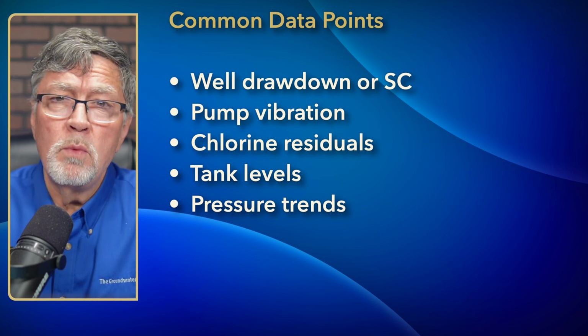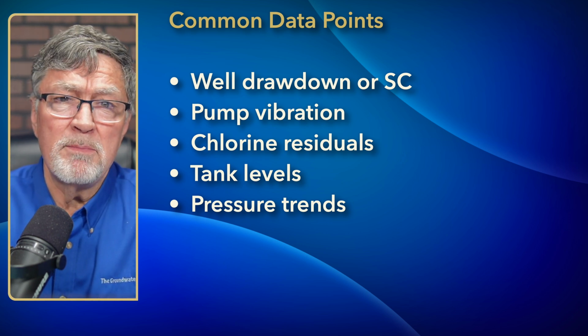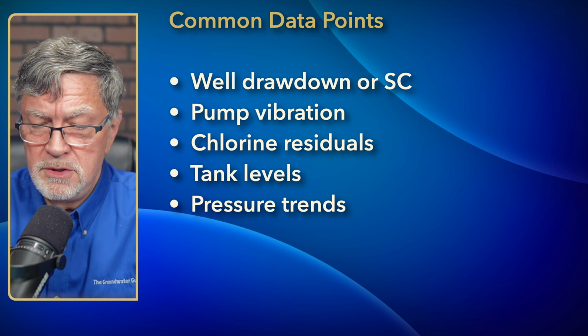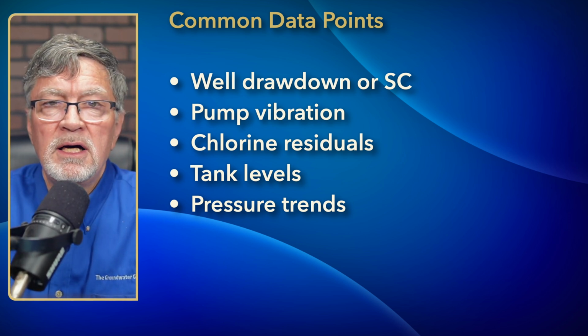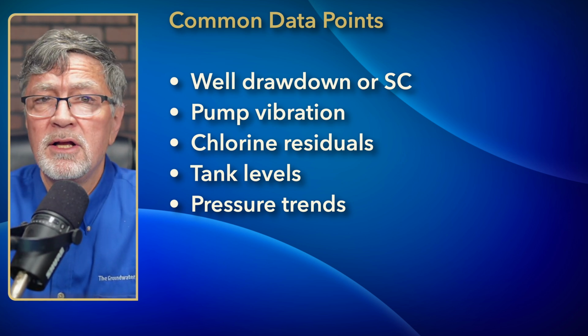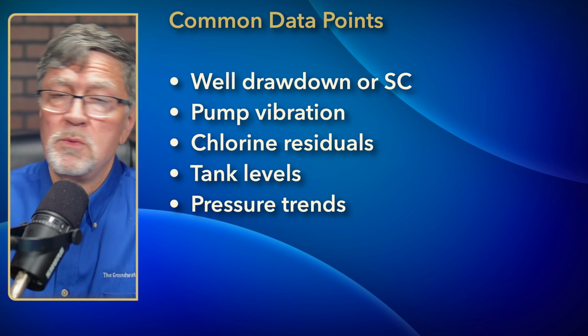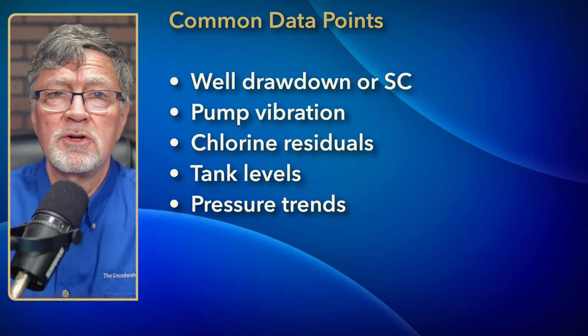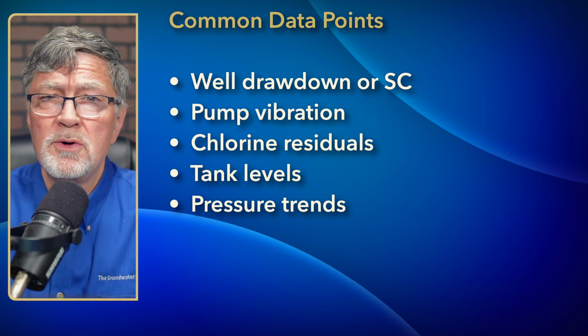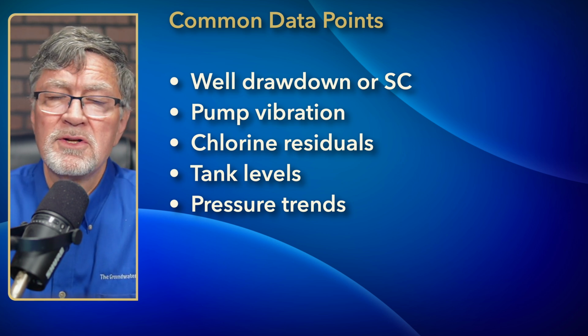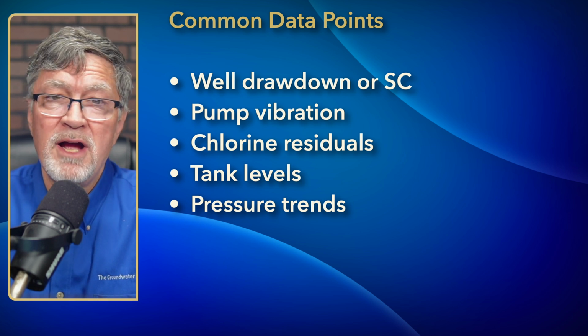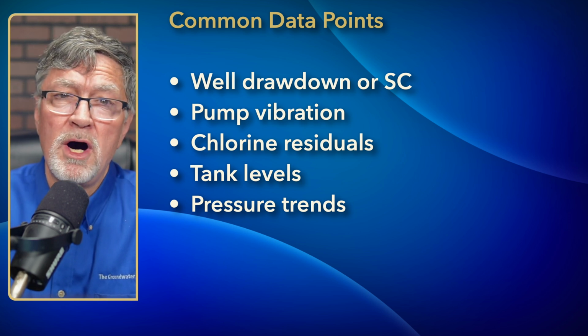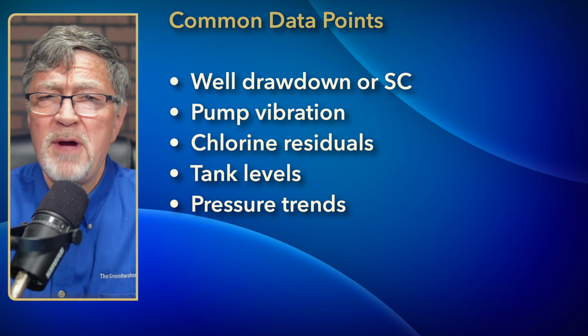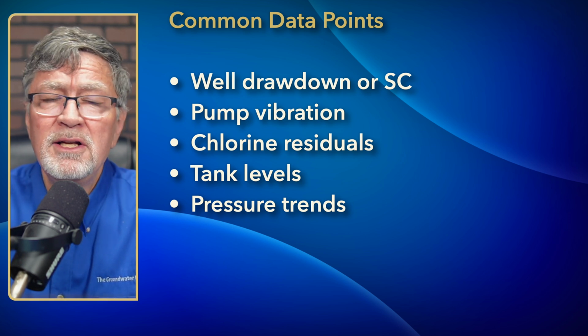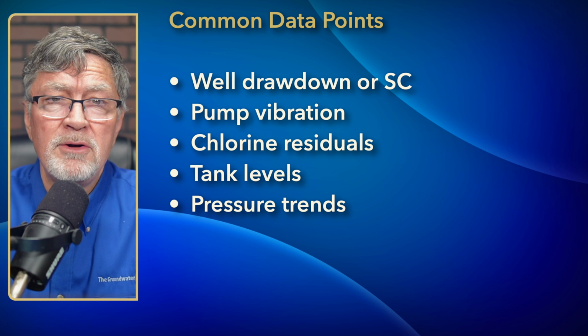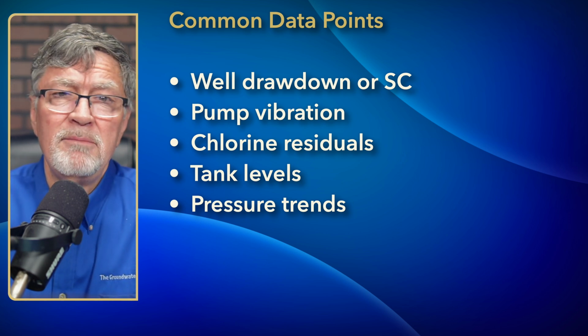So now you're predicting when you're going to lose enough specific capacity in the well that you'll need to rehab it, and you're going to lose flow if you don't — sometimes the well will just seal up if you don't rehab in time. So we really want to look at those numbers and measure them. That takes drawdown — how much drawdown you have, which is static water level minus pumping water level — and your discharge rate. Specific capacity is very easy to calculate; you just need to know your drawdown in the well and what you're pumping, and make that calculation.